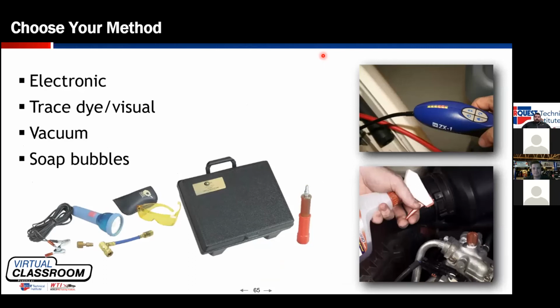You can see in this picture, we're using a liquid leak detector, spraying it around the service port cap, and we can see that compressor manifold foaming. So there's a crack in the compressor manifold at that point. Are we going to do something like forming gas? Are we going to use nitrogen? Pick what method you're going to use.